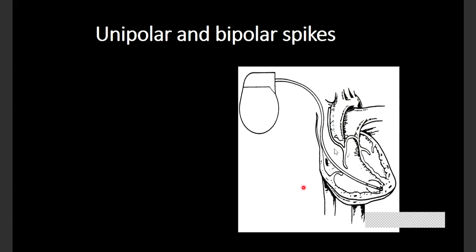So, I already talked to you about unipolar and bipolar spikes. Traditionally, in unipolar spikes, the anode is here and the cathode is here. So the generator is a part of the system, and then you get a huge spike. In bipolar leads, you have a ring electrode and a tip electrode, and the current flows between the ring and tip electrode, and that generates a very small spike. So, most leads today are bipolar leads. Sometimes we do program into a unipolar configuration, but because most leads are bipolar leads, it's very difficult. Sometimes you will find a spike, but it won't be a really significant spike. So in today's ECGs, don't look for really big pacing spikes.